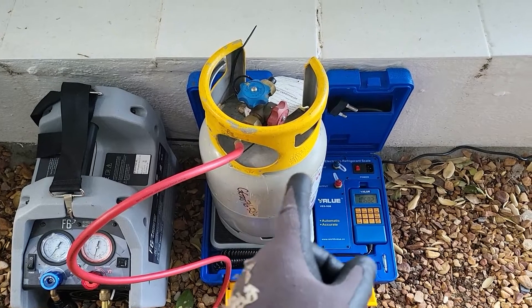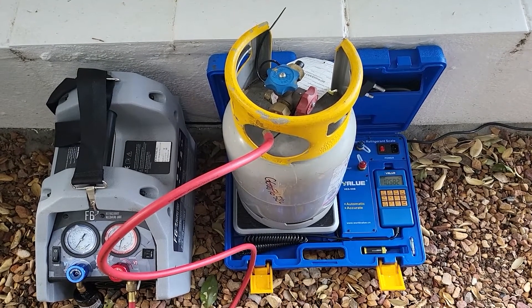We've got a VALUE scale to work out exactly how much gas is being recovered. By recovering and measuring the gas, you can see exactly how much was in the system and whether it had been undercharged or if there's potentially a leak. That is a very important process — it really helps when doing compressor changes to diagnose exactly why the compressor failed.